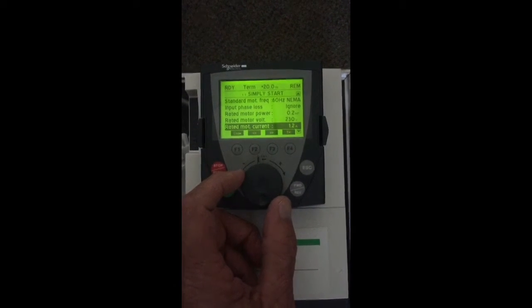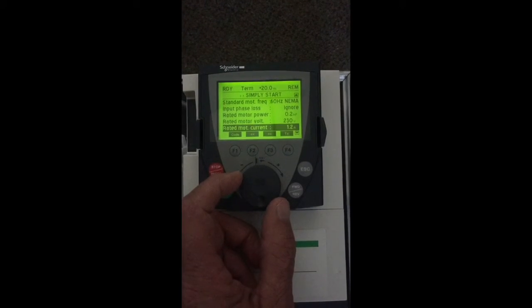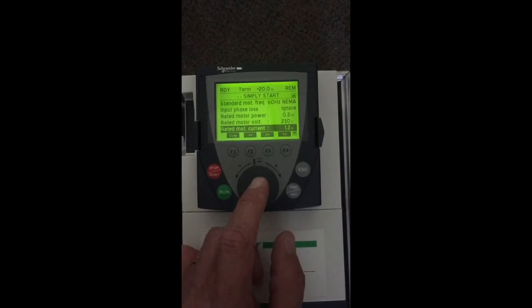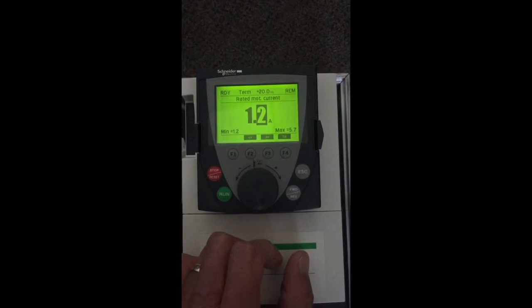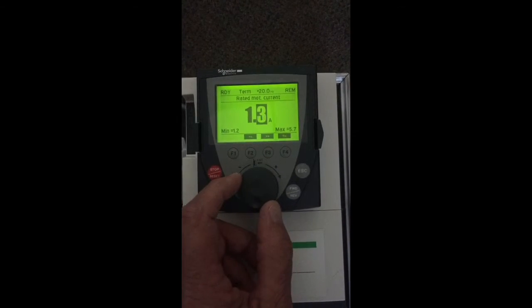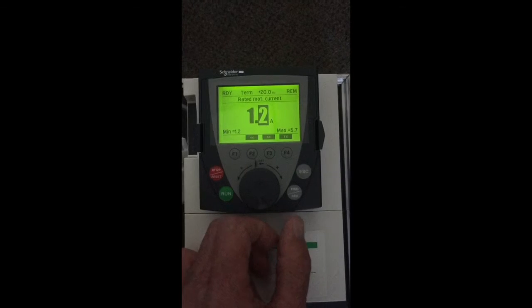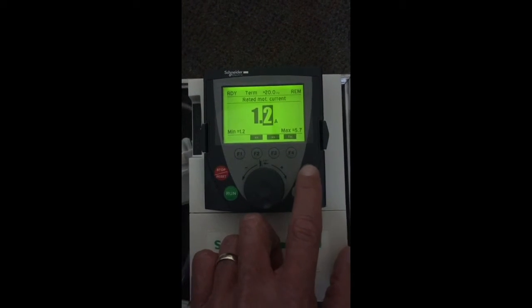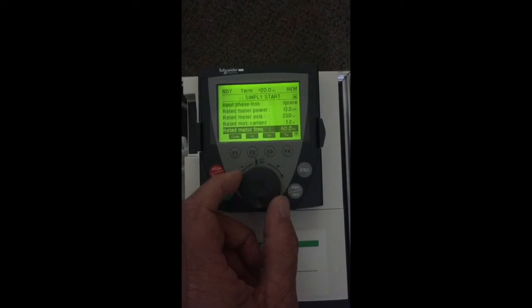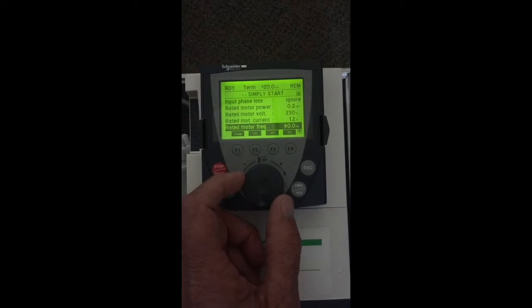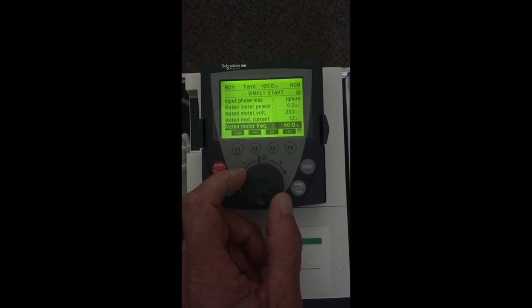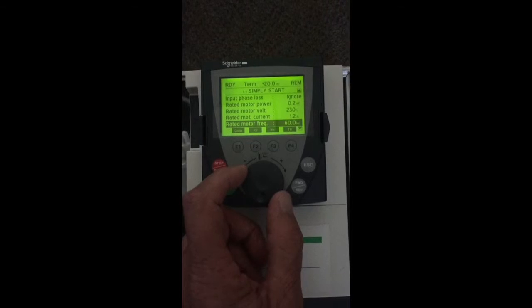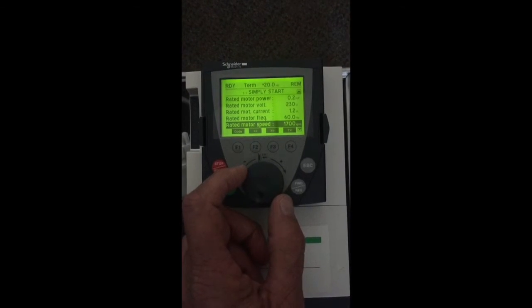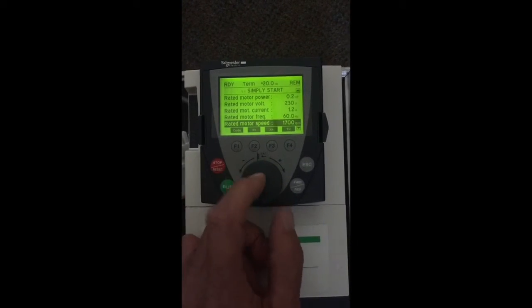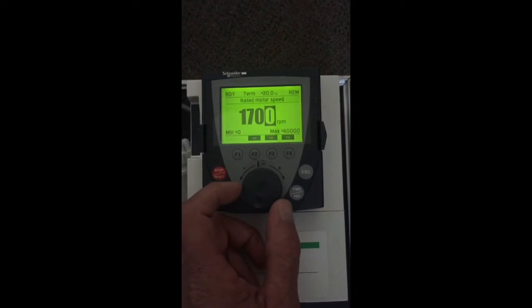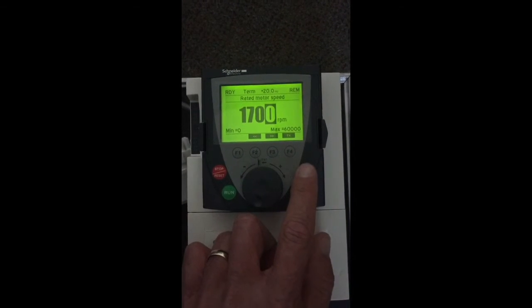Motor current, you will pull this data from the nameplate of the motor, set this to the full load current of the motor. To adjust, simply go into that parameter, move the dial accordingly. Motor frequency, most of our motors are 60 Hertz, shouldn't have to change that. Motor rated speed, possibly have to change your RPMs to the motor data.